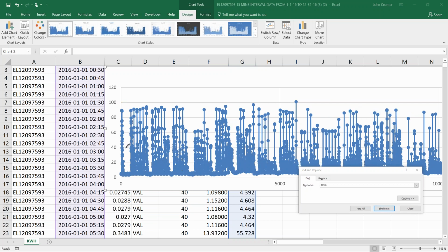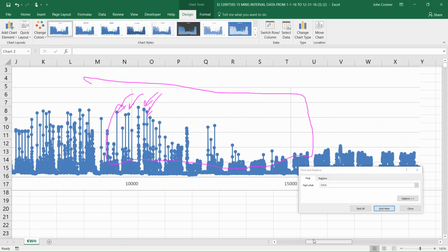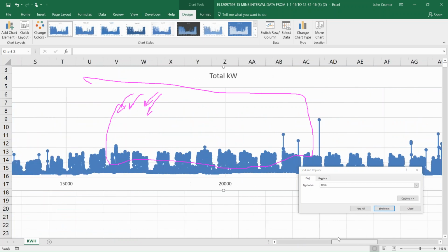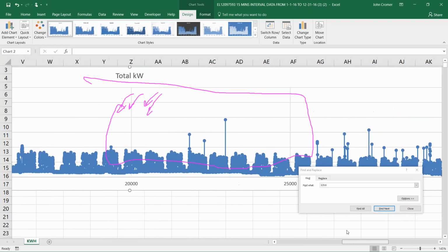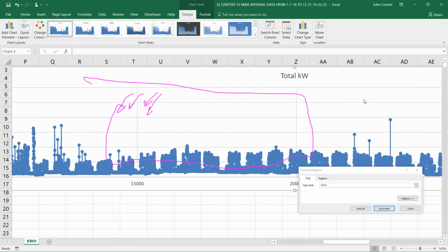This is like the best you could hope for in a battery bank, because again, we're only going to be running the batteries for an hour or two a day, and we can take this demand all the way down to something very substantial. Then again, when the summertime rolls around, we don't have that heating, and now almost counterintuitively, his building demand in the summertime drops substantially.